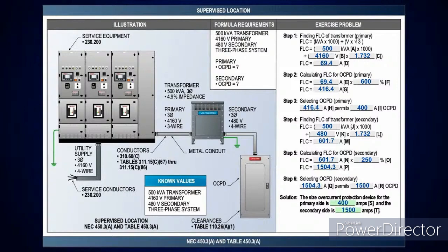Then if I come over and do the secondary, come across, looky there, 250%. There's no superscript 1. That means I'm going to drop down. Right. Okay. So I'm going to do the same calculation. I still came up with 69.4 at 600%. It's 416.4 amps. I didn't have my superscript 1 there. So I said anything over 125% drop down unless there's something telling you otherwise. So the next size below that for table 240.6A is a 400 amp overcurrent device.